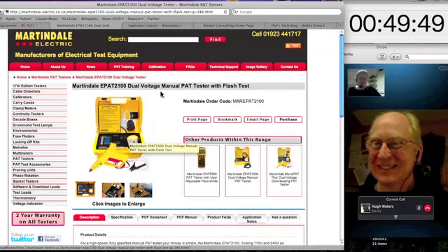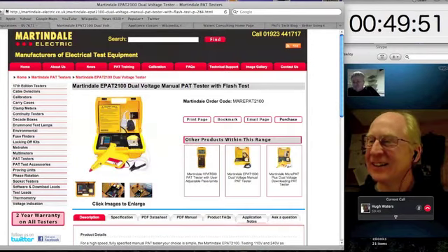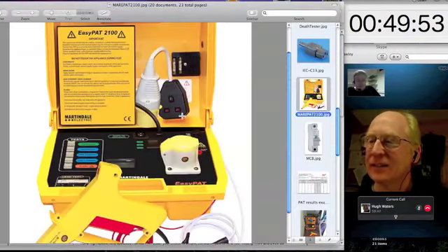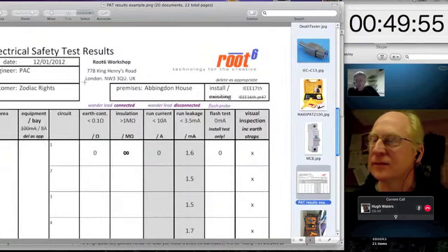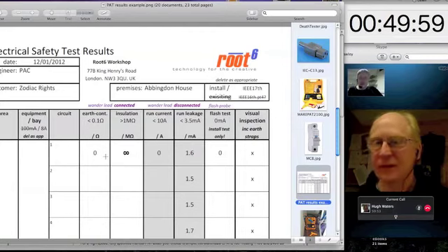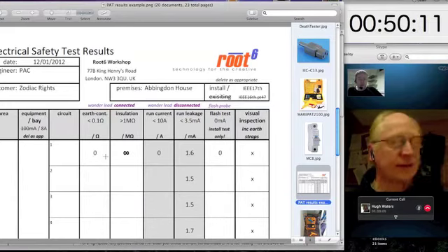I suspect I pinched one from the other. But, so the first button. So in fact, let's go back to our test sheet. The first button. So we've got our Pat tester behind the cabinet, and we're powering the Pat tester off the incoming supply for the cabinet, and we're powering the cabinet off the outgoing supply from the Pat tester.